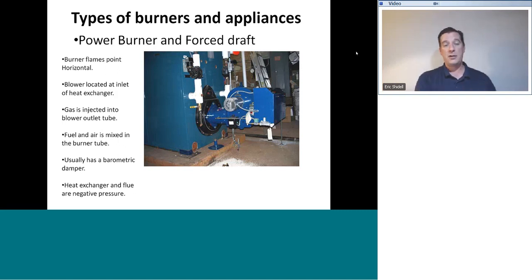Gas is injected into the discharge of the fan to mix with the air, and it travels down a tube of the burner with a flame propagating at the end, shooting out horizontally. It's like a giant flamethrower, essentially. However, this might make you think that the heat exchanger and the flue are now under positive pressure, but they're not. They are still under negative pressure. Here's a closer-up shot of that burner.